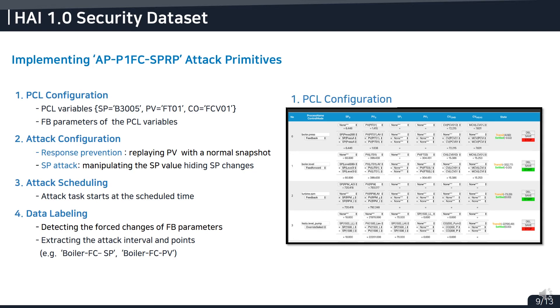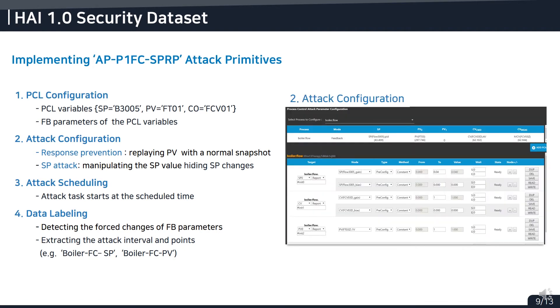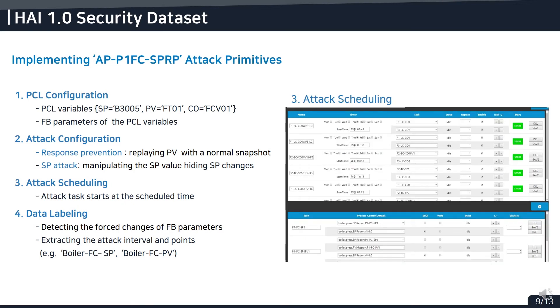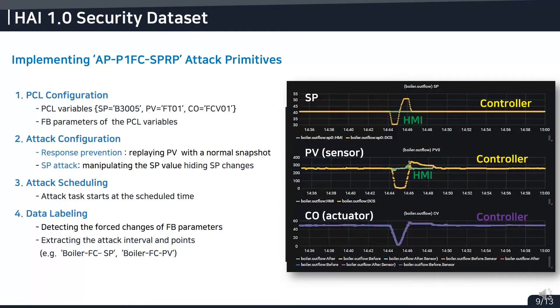First, we have to configure PCL variables and their function block parameters. This means that all remote access points are identified to force the function block parameters. Next, we configured attack primitives with response prevention and setpoint attack. This will replay a normal snapshot of the process value and force the setpoint into any value. All attack primitives are automatically executed while scheduled at a specified time. Finally, the attack tool records all forced changes of the function block parameters so we can easily extract the precise attack interval and points.